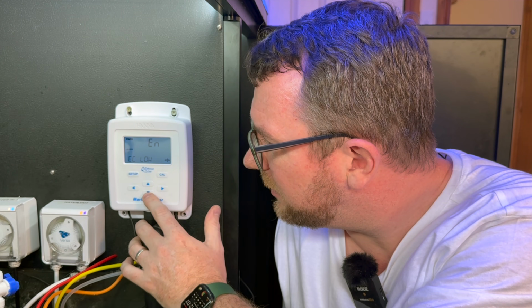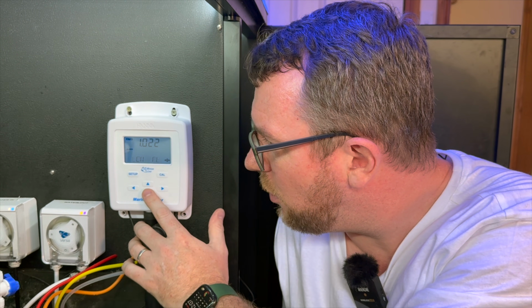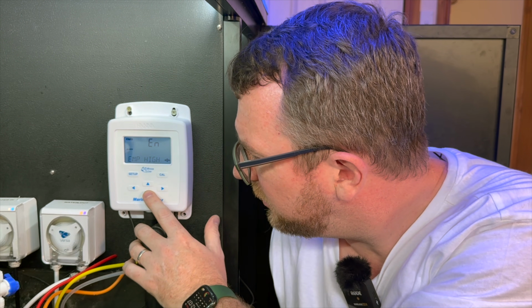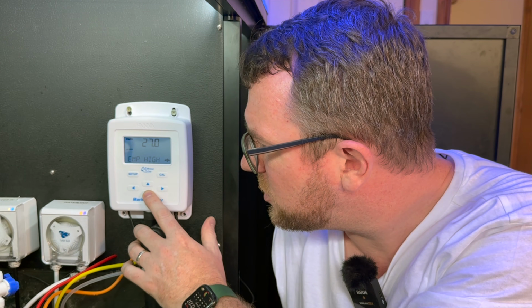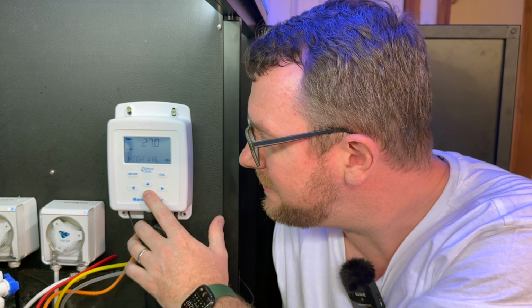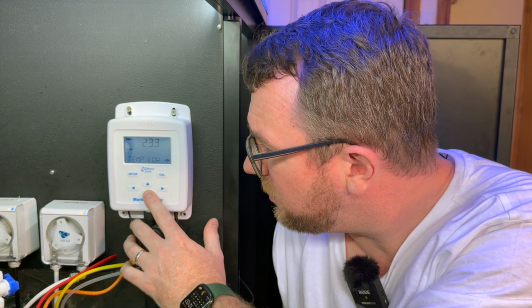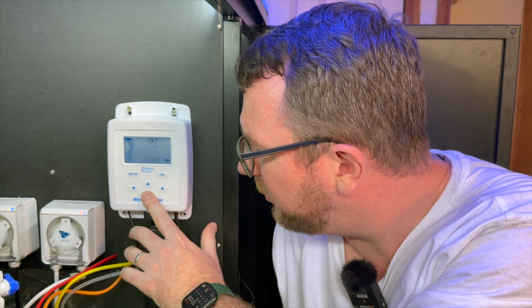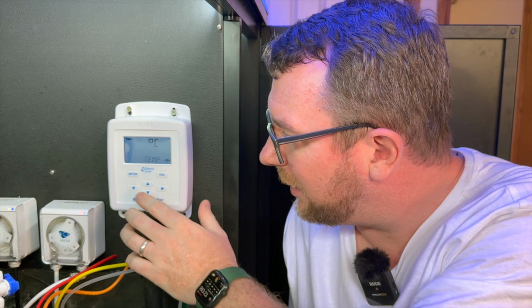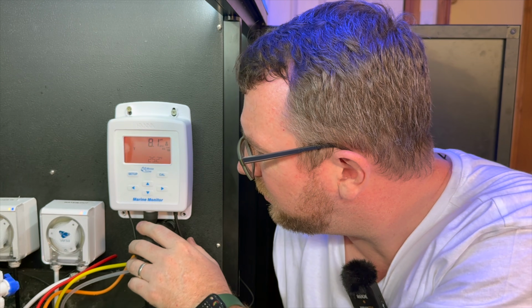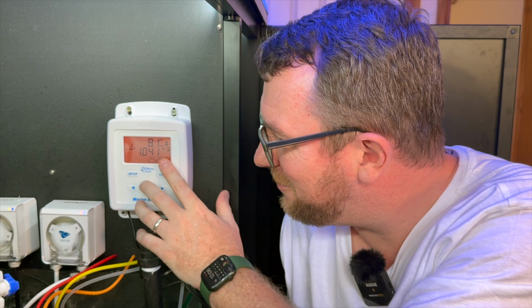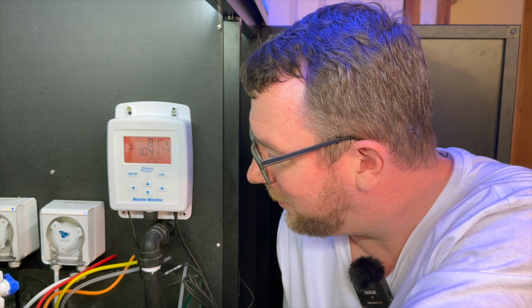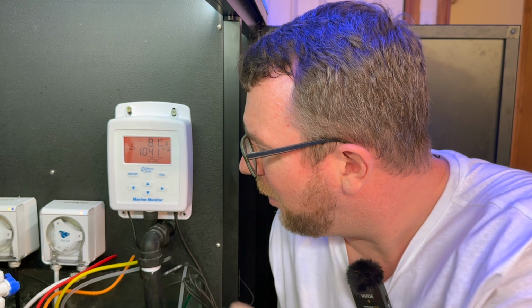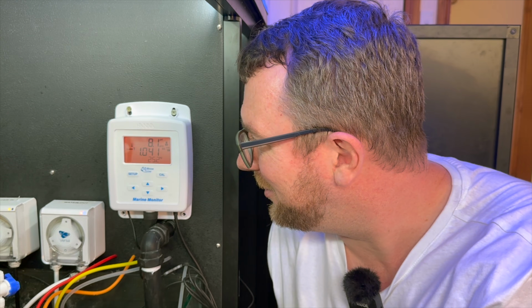Then we've got the salinity low alarm. It's currently set to 022. That sounds good. We've got the temperature high is engaged, it's set to 27.0. Happy with that. Temperature low is engaged and set to 23.3. Happy with that. And then we're back to temperature again. So I should be able to press left. We go back to our display, and we are still reading a salinity of 1.041, which is quite high. Looks like we may need to calibrate the device, and I'll get the instructions out and we'll go through that process right now.